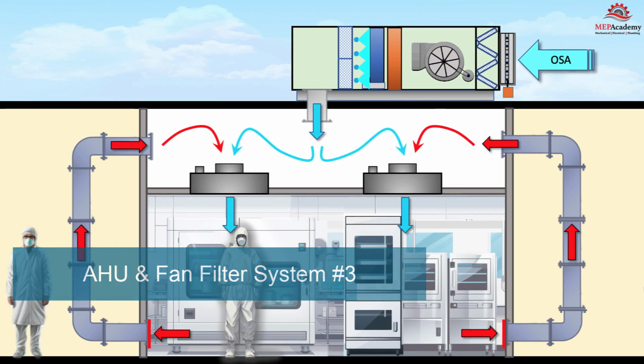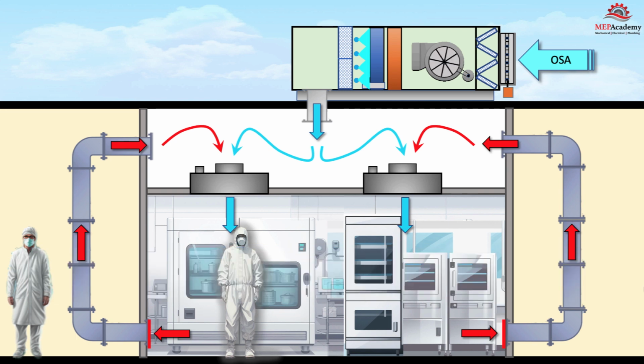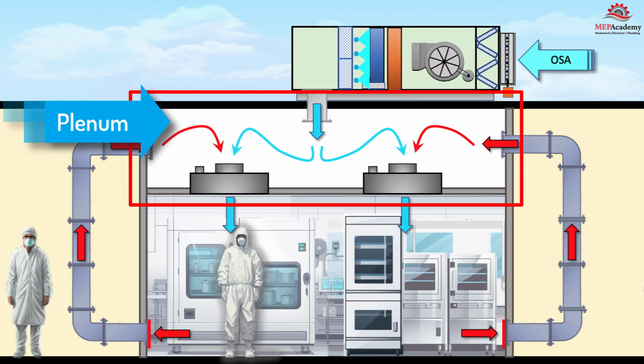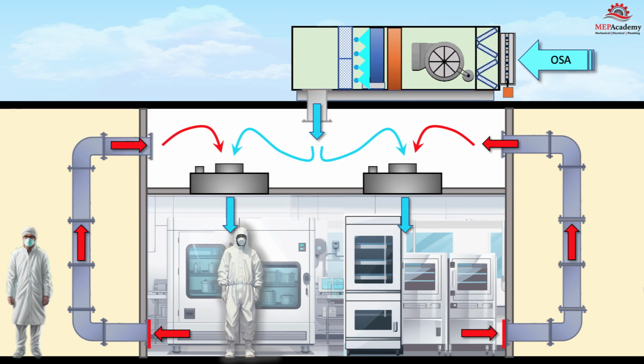Air handling unit and fan filter unit system number 3. In this third system configuration, the air handler dumps its supply air into a sealed plenum area where the fan filter unit draws air from. The return air is drawn into the plenum space by the fan filter units.